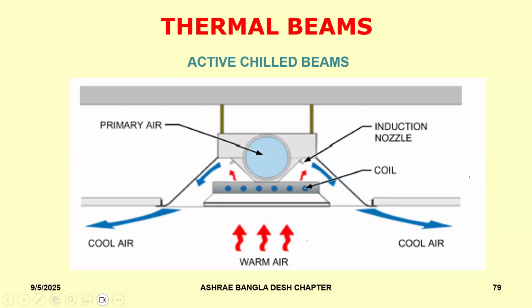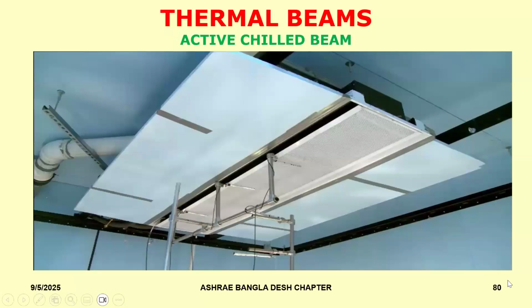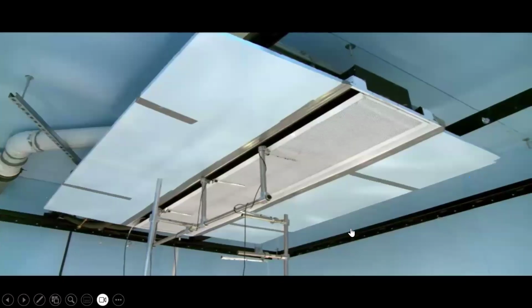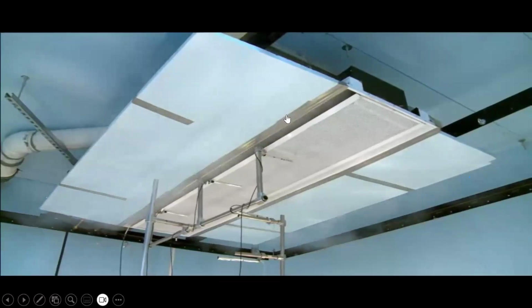So this is generally used well in conjunction with a VAV unit that I showed you, which can modulate the amount of outdoor air required based on occupancies and things like that. So this is what an active chilled beam is all about. And I've got a picture of an active chilled beam under test here. So this is the beam, and that's a coil here. And this is the slot through which the air will exit. And this is your duct, which is bringing the outside air. So we're just doing some measurements in terms of velocities and noise, etc. You can see the air is actually exiting from these two and then spreading. So you need to have this ceiling so that it can actually spread across the entire space.